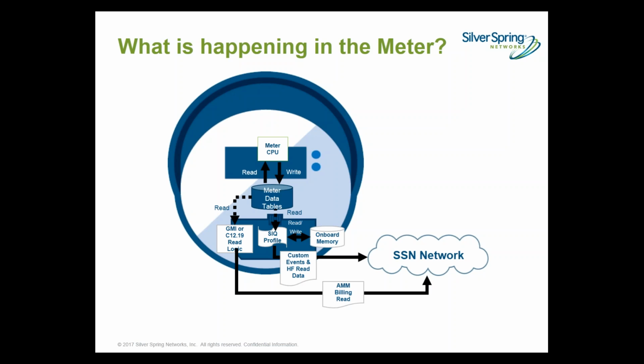This Sensor IQ application enables a lightweight, parallel meter data collection path for new data elements or even high granularity data for existing elements. It stores that information on the network interface card for processing, and then we'll either send custom alarms or that data can be gathered at whatever interval makes sense over the network. This can be deployed and changed on the fly without ever impacting the meter program or read path.